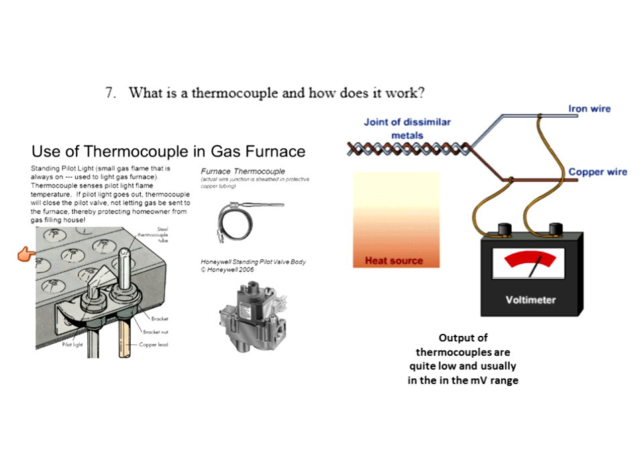And that pilot has to be lit to ignite the main burner over here. If this pilot gets blown out, for example, a windstorm comes and blows a little bit of air down into the chimney and blows the pilot out, that pilot's getting gas all the time. And that could cause a lot of unburned natural gas to gather on the floor of your cellar. And then somebody comes down and turns a switch on, or comes down and tries to ignite the pilot, and that will cause an explosion.